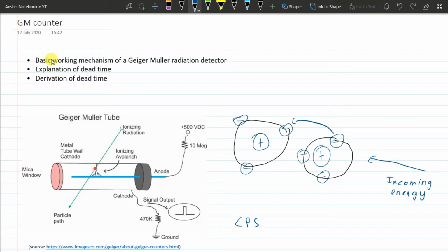Okay. So this is the construction of the Geiger-Müller tube, and now I'll explain how it is used to detect radiation. What happens is you have some form of ionizing radiation come in. This ionizing radiation interacts with the atoms inside the tube. Now I would like to note that the ionizing radiation could be of any kind. It could be alpha radiation, beta radiation, or gamma radiation. The only requirement is that it has to ionize the atom, or ionize the electron.